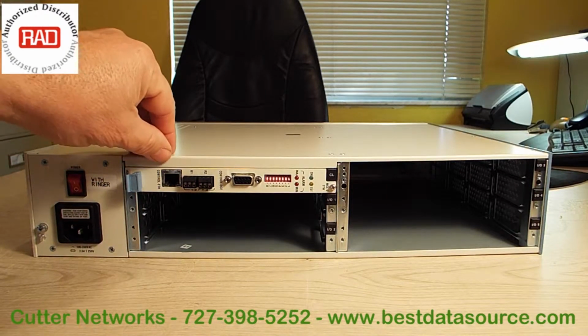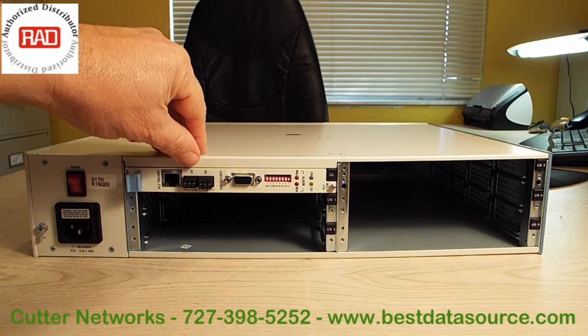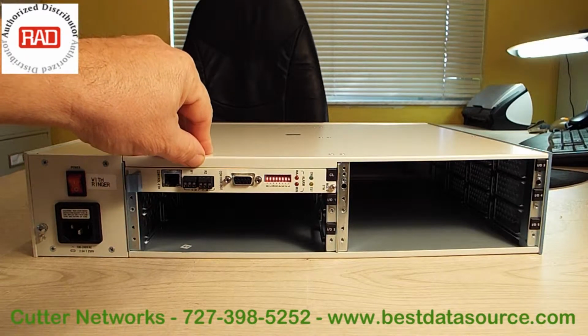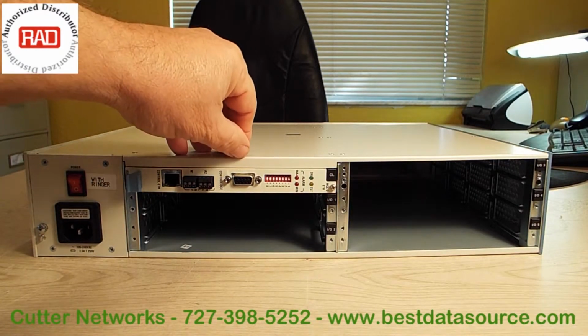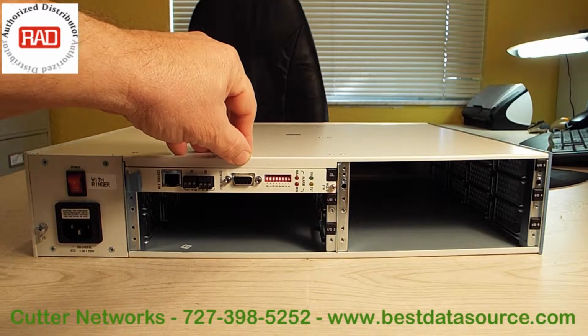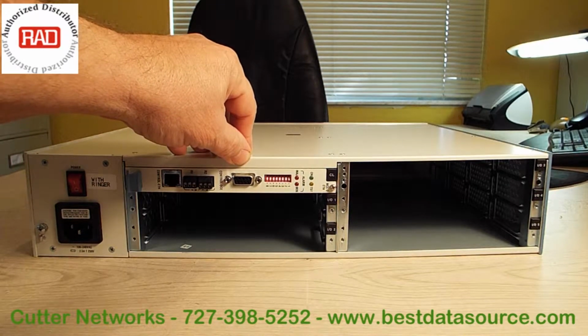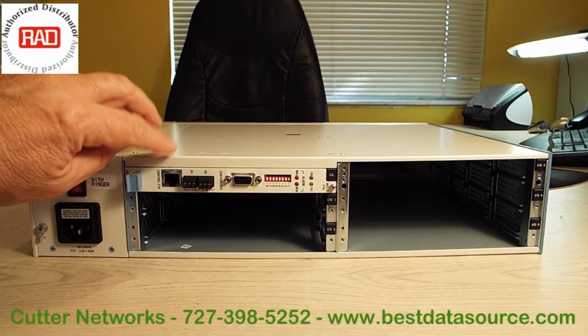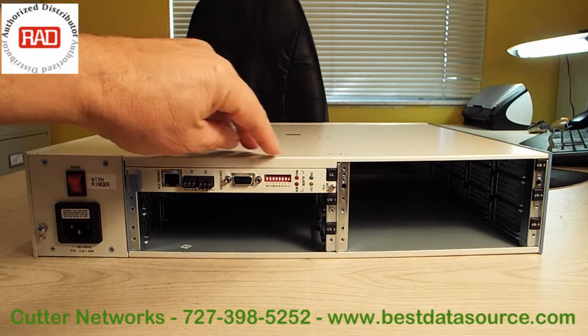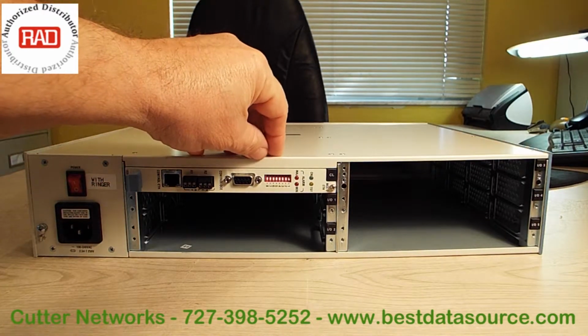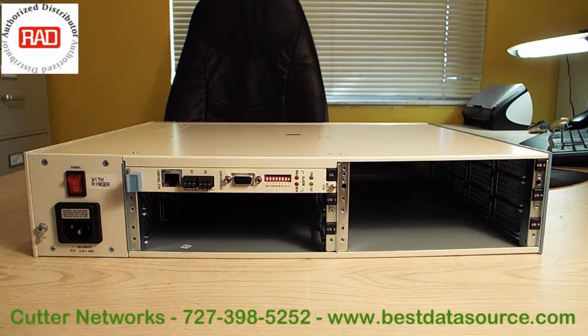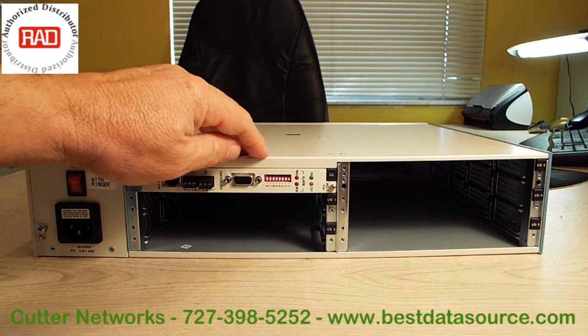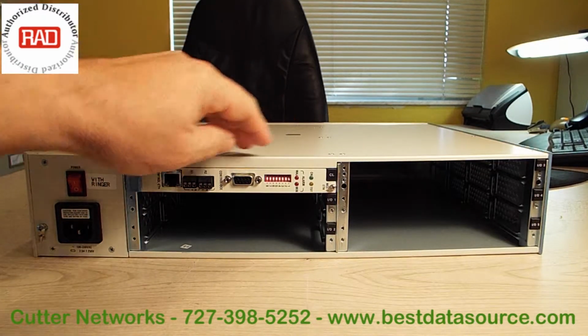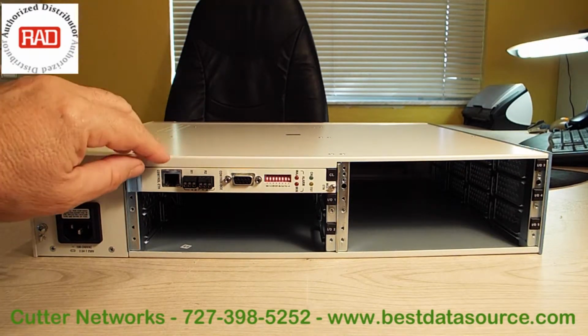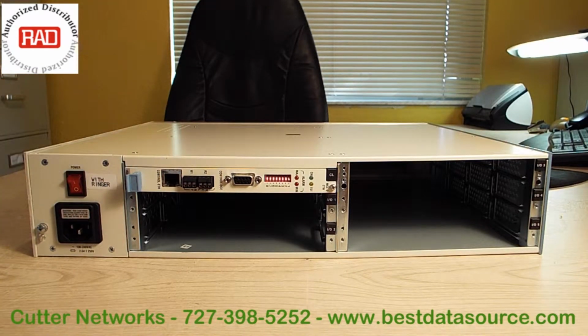On the common logic card, we have an Ethernet control port. We have 2 alarm dry contact relays. We have a serial connection used for initial configuration when you're first assigning an IP address. Thereafter, most of the management will actually be done via this port. And you have these dip switches, which are primarily used with the upgrade of software revs and things of that type. They have some other features as well, but as I said, most of the management, once you initially get it set up, is done via this Ethernet control port.